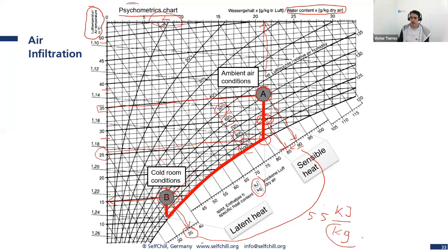Okay, so now we have more or less understood how to calculate this. Now we need to know how much kg of air we are going to cool down, and how much volume is going to go inside the cold room. As a recommendation, we can consider 2 renovations per day. If we have 20 cubic meters, then 2 times 20 cubic meters equals 40 cubic meters of air that we are cooling down within the cold room. This way we can calculate the amount of energy that we need.